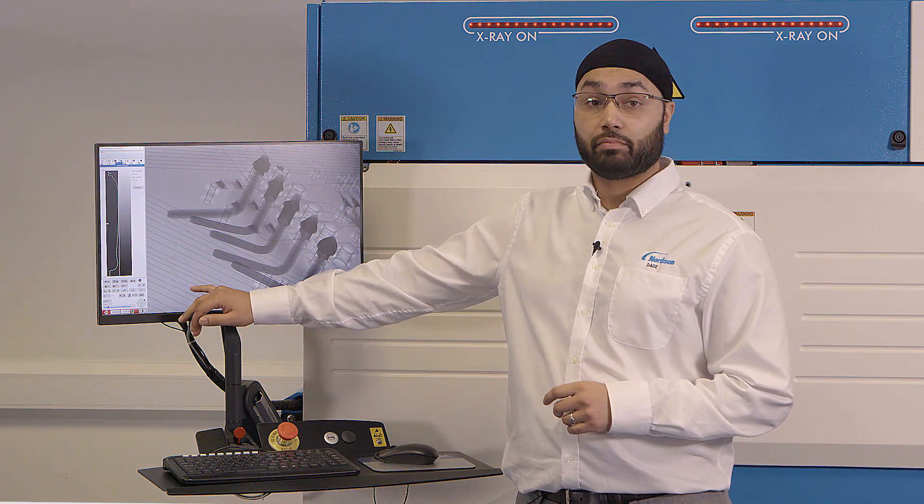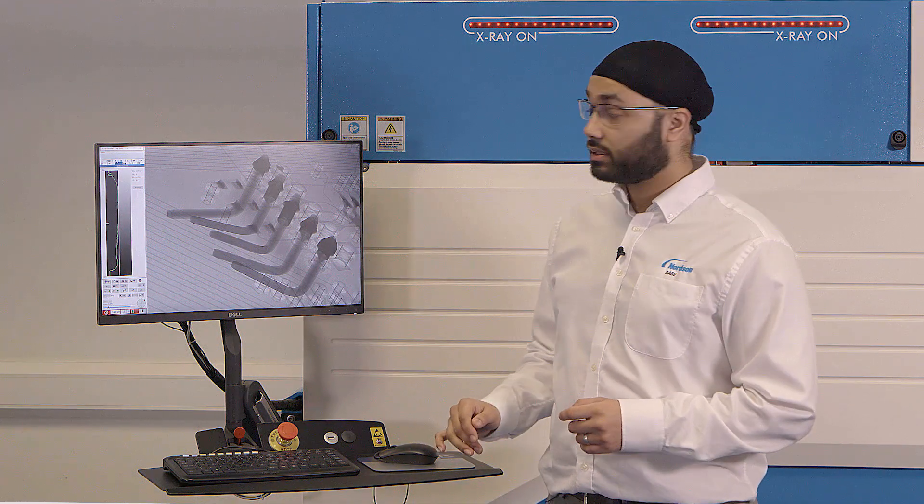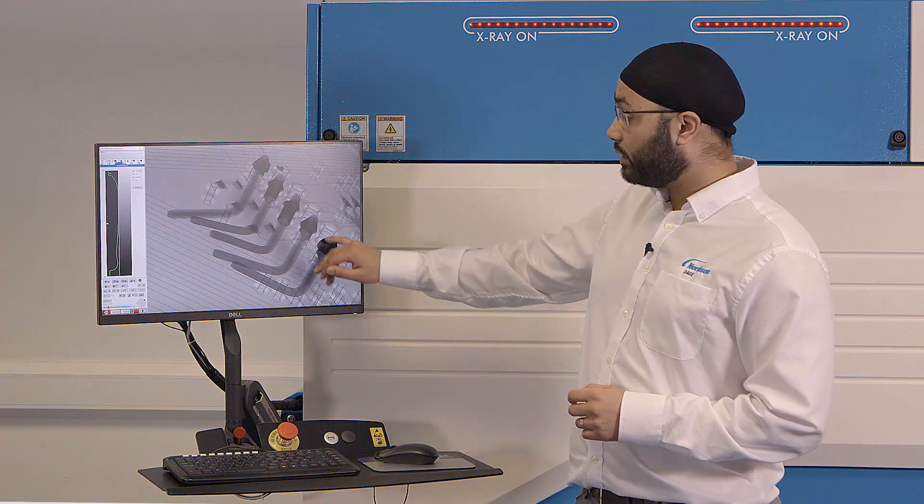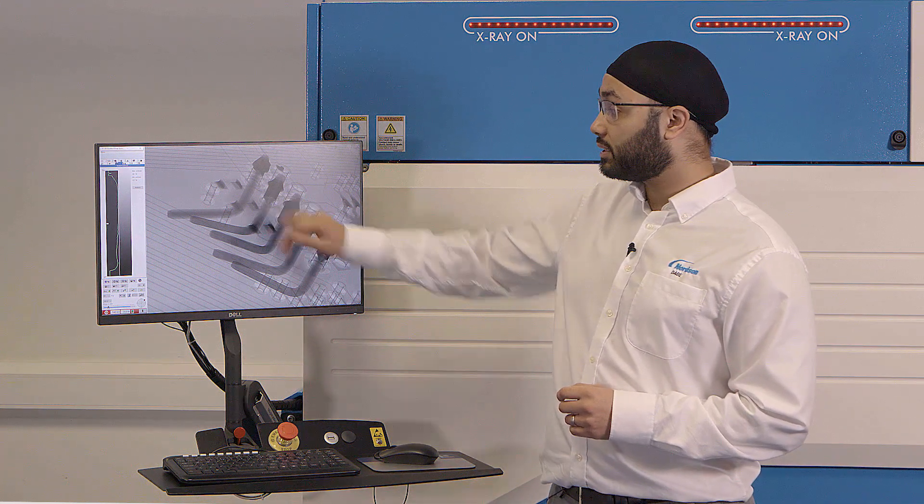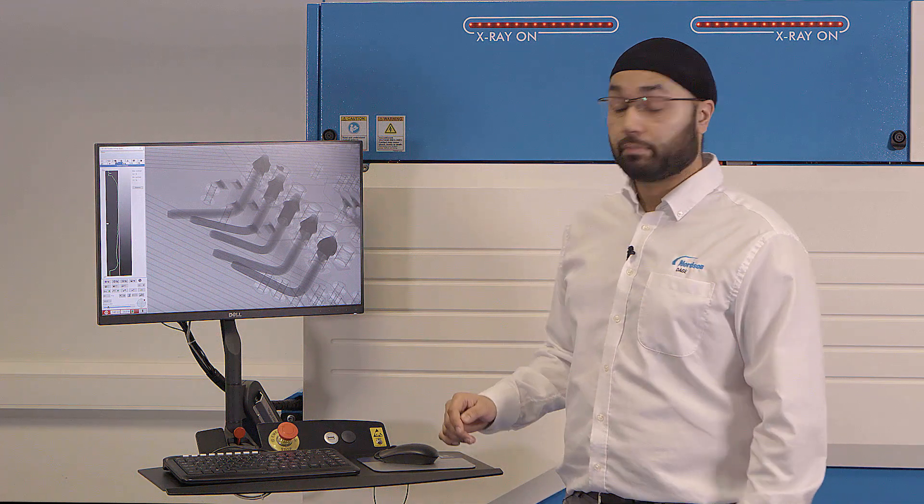At low x-ray power we see great contrast on the thin components like the PCB tracks. However, I'm also interested in the dark components and to bring out information in this area I need to increase the power.